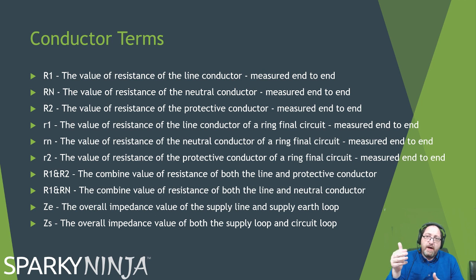So R1, Rn, R2, these are the measurements of a cable. A line is R1, a neutral is Rn, a protective conductor or an earth is R2. If I'm on a ring final circuit and I've taken the board off, I've got my line going off, I've got my line coming back, that returning cable, whilst it's the same kind of test, that is known as a little r1, so it's a returning measurement. And then I have little rn for the returning neutral and the little r2 for the returning CPC.